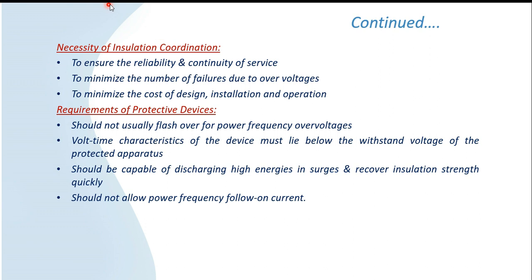The necessity of insulation coordination is to ensure the reliability and continuity of service and to minimize the number of failures due to over-voltages. Insulation coordination also minimizes the cost of design, installation, and operation by suitably selecting the insulation levels for different equipments. The main requirements of protective devices are that they should not usually flash over at normal working conditions like normal power frequency over-voltages.